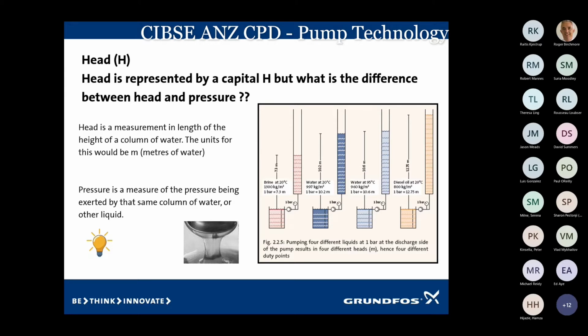performance curve at 20 degrees. So always just consider, if you're pumping glycols, what effect it's going to have. If you're pumping propylene glycol or ethylene glycol, in a reasonable percentage, 30%, and it's getting down in temperature, it will impact on the performance curve, it'll impact on the power curve, and the efficiency.